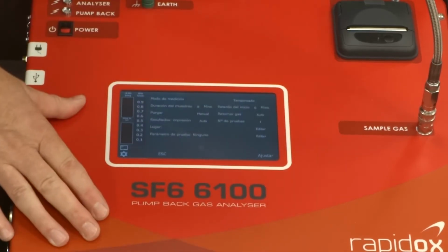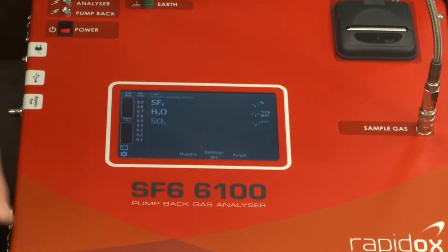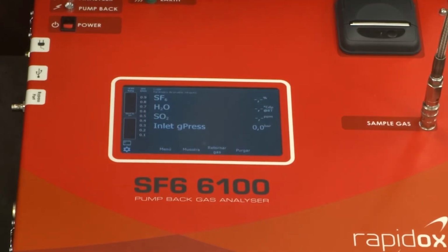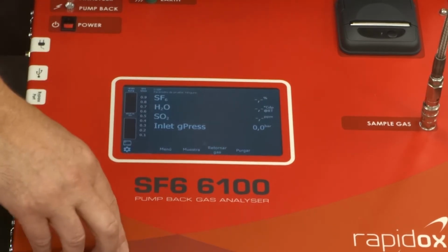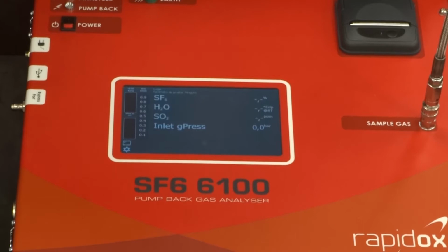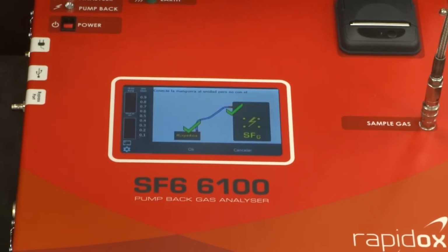Once I've set my sampling screen up, I'll press the store button and come back out to the main panel, and then it is just a case of, when you're ready, to do a measurement. Now I've done all the settings correctly for the analyzer, they will be stored for the rest of the day, and I can now do a test. So we simply press the test button and we will get a screen asking us to connect the hose from the Rapidox over to the switchgear or circuit breaker or transformer and make the connection.